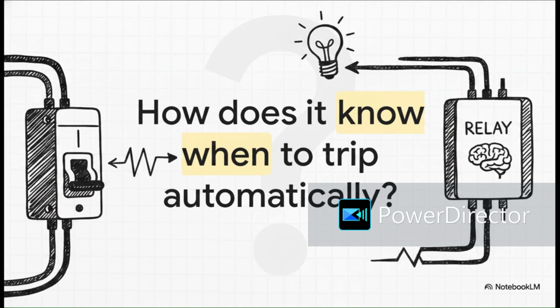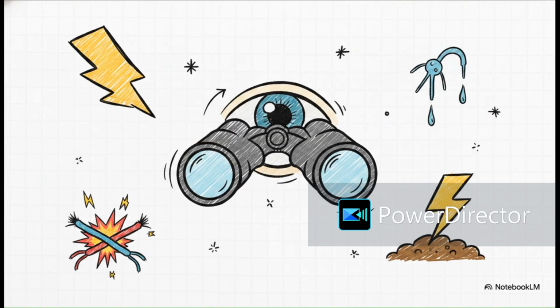You can think of the relay as the brain constantly monitoring the system, while the breaker itself is just the muscle, patiently waiting for a command. That relay watches continuously, 24/7, for sudden, highly dangerous electrical abnormalities. It's constantly looking for an overcurrent, way too much power surging through the system. It's looking for undervoltage, a sudden short circuit, or maybe an earth fault. The specific type of relay really depends on your exact setup, but its job is always the same, to stand guard. This creates a brilliant automated safety loop.